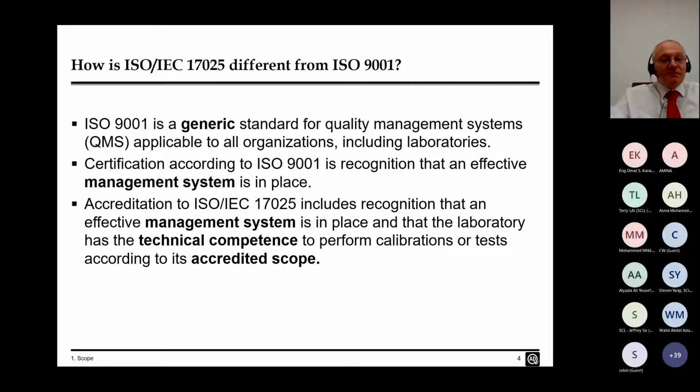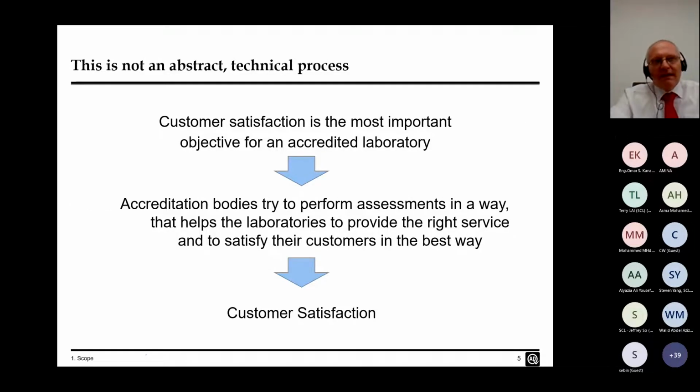So it's a big step from 9001 to 17025, and many quality managers who think they know all about 9001 and maybe do know 9001, when they come into laboratories, misunderstand that this is not certification, this is accreditation, and we're looking at a much higher threshold for acceptance. And we've had a number of issues in the UAE in the past where the quality managers were really not aware that accreditation and certification are very different.